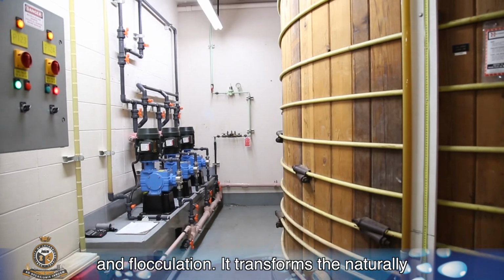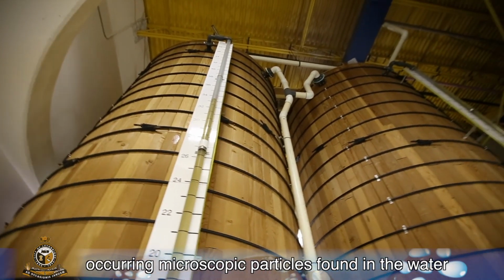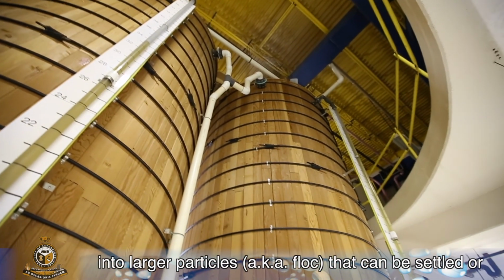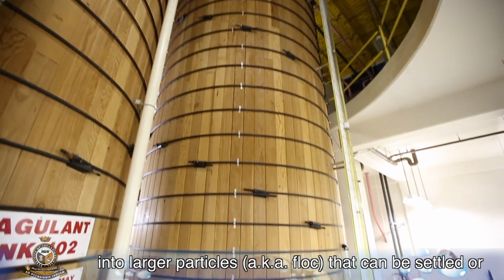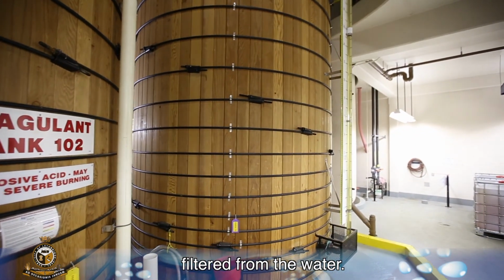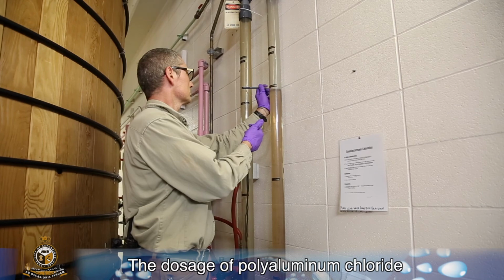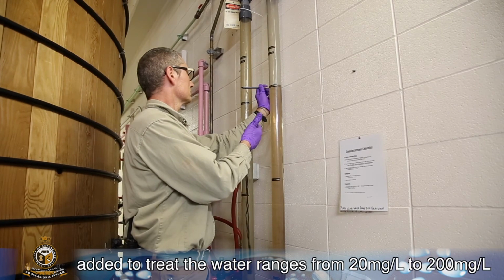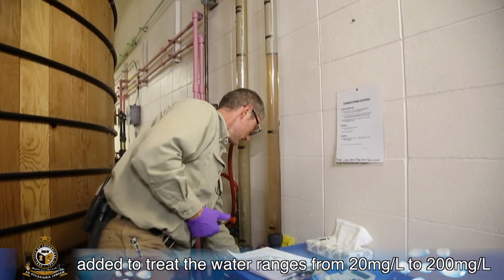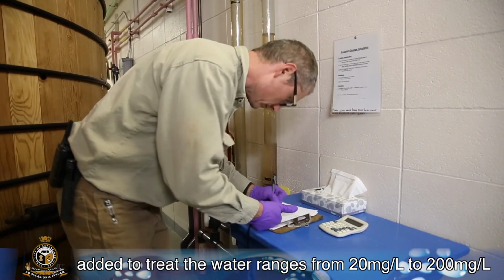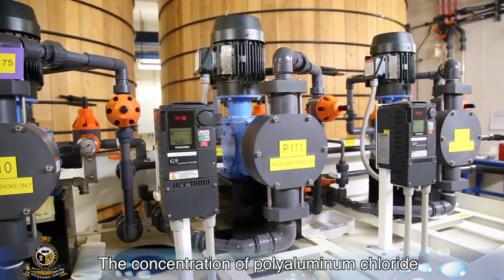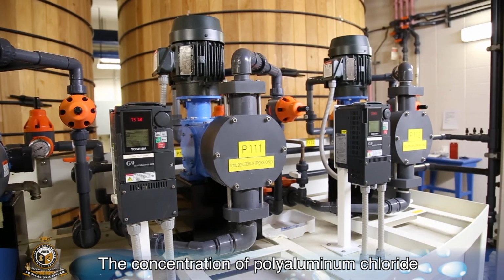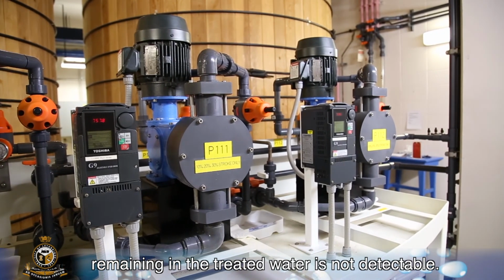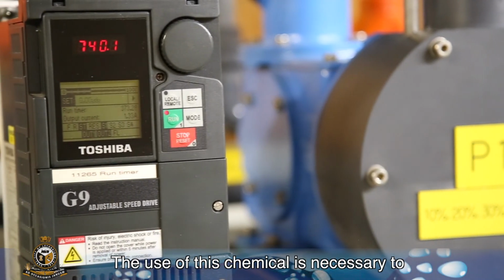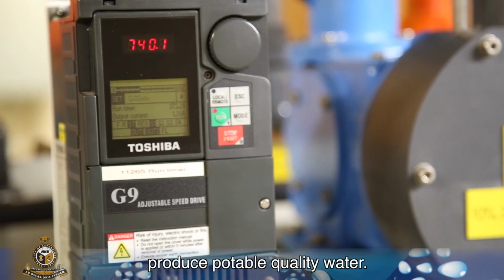It transforms the naturally occurring microscopic particles found in the water into larger particles, aka floc, that can be settled or filtered from the water. The dosage of polyaluminum chloride added to treat the water ranges from 20 milligrams per liter to 200 milligrams per liter, depending on the river water quality. The concentration of polyaluminum chloride remaining in the treated water is not detectable. The use of this chemical is necessary to produce potable, quality water.